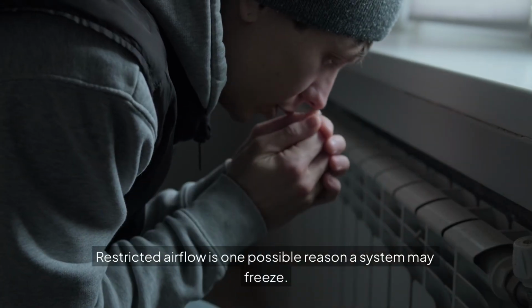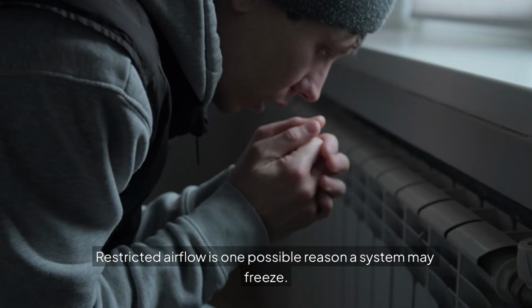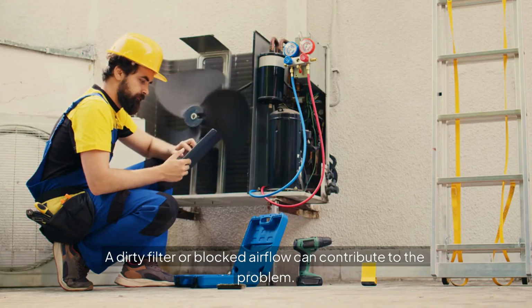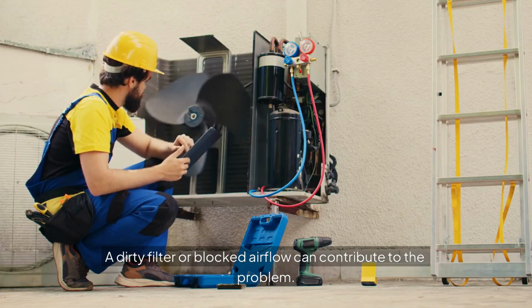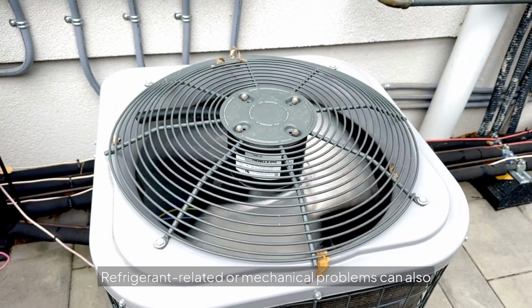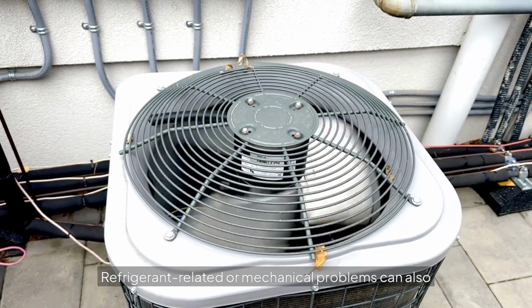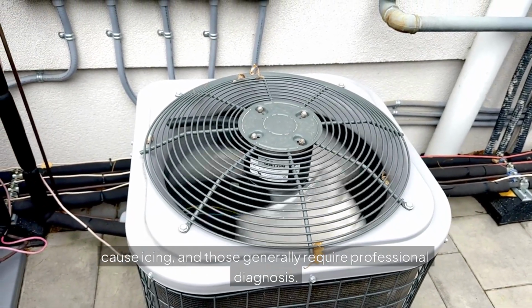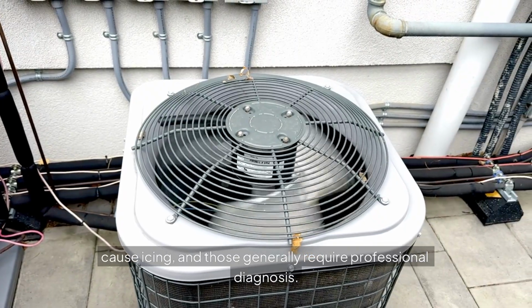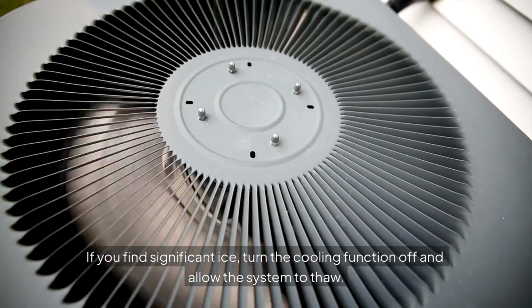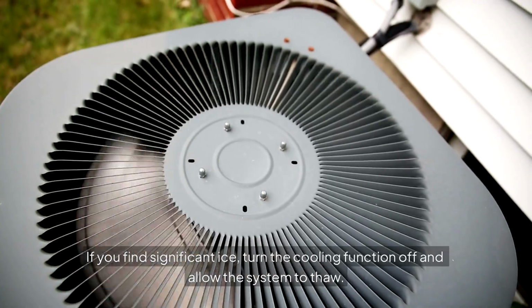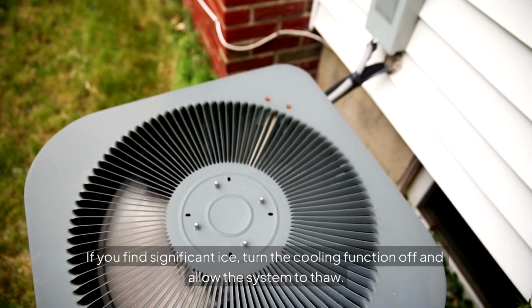Restricted airflow is one possible reason a system may freeze. A dirty filter or blocked airflow can contribute to the problem. Refrigerant-related or mechanical problems can also cause icing, and those generally require professional diagnosis. If you find significant ice, turn the cooling function off and allow the system to thaw.